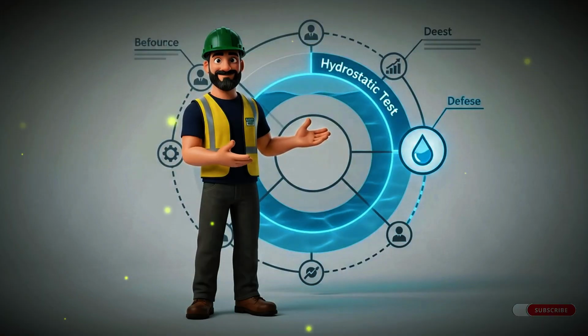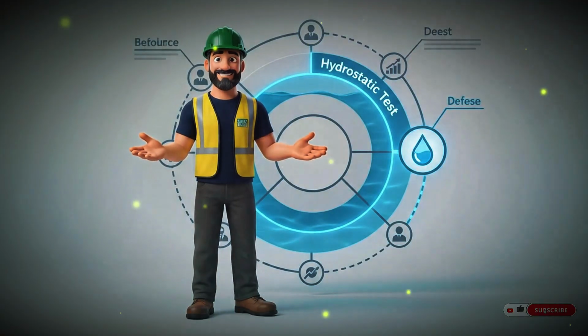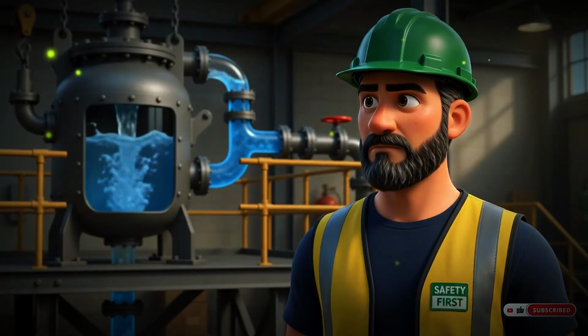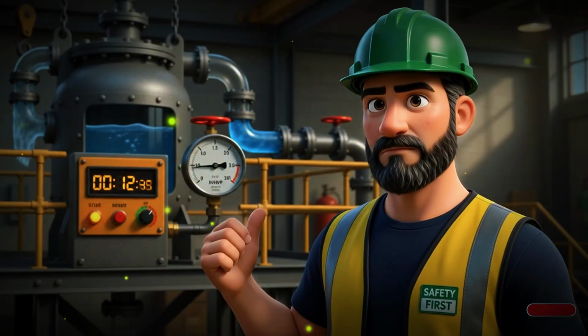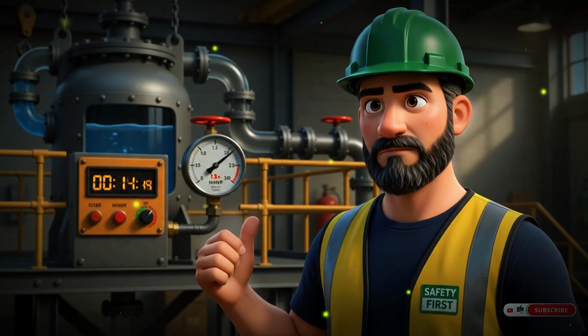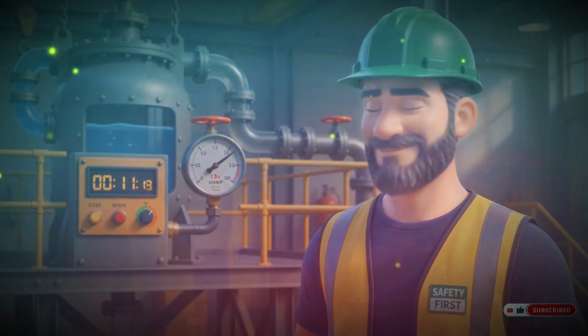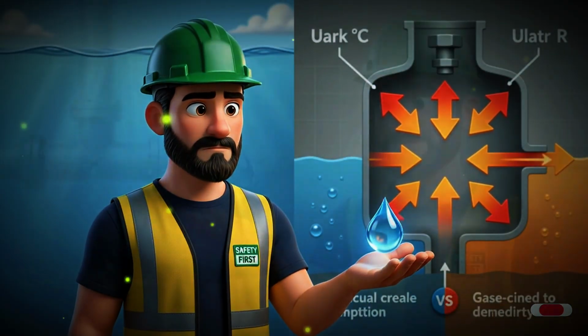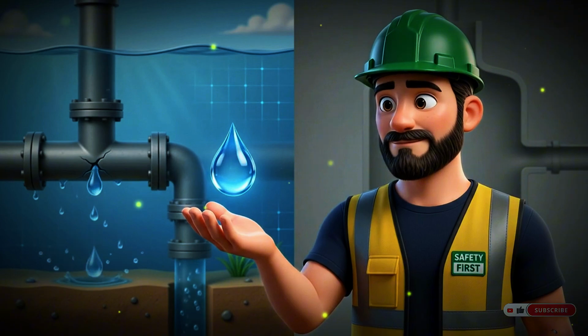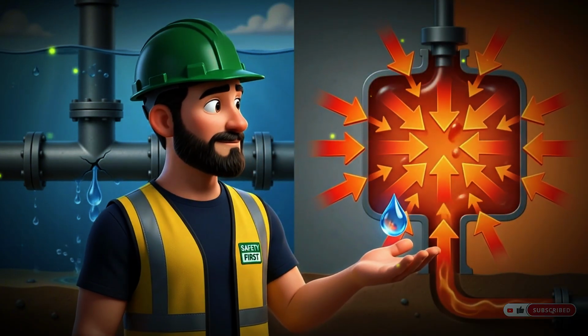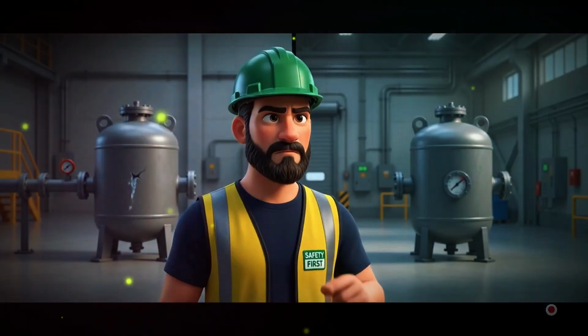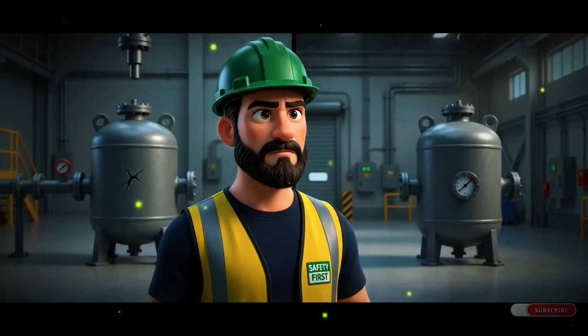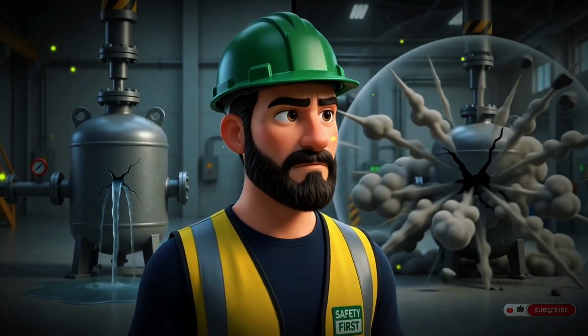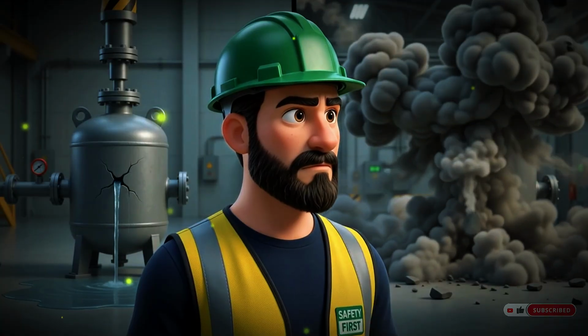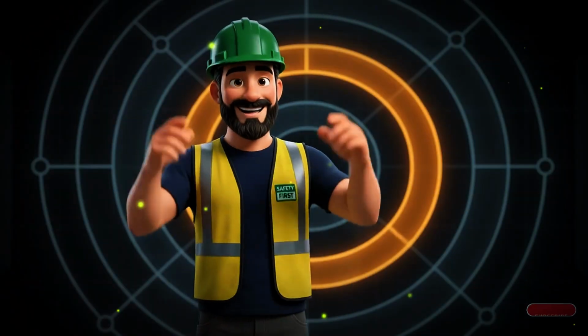The third layer is the hydrostatic test. Before entering service, every certified vessel must be pressurized with water, not the process fluid, to 1.3 times the maximum allowable working pressure, and hold that pressure for a defined period without any leakage or deformation. It is the final verification before first use. And it is done with water precisely because, unlike compressed gases, water does not store elastic energy. If the vessel fails during the hydrostatic test, the failure is localized and controlled, not explosive.